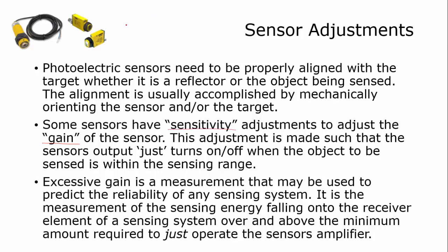You'll mount your sensor, you'll have your object that you want to sense, and you'll have it at the distance that it's going to sense. Then you'll adjust the sensitivity, and it's usually a small screwdriver type potentiometer, so that at this distance the sensor just either turns on or turns off, depending on the mode that you have it operating in.